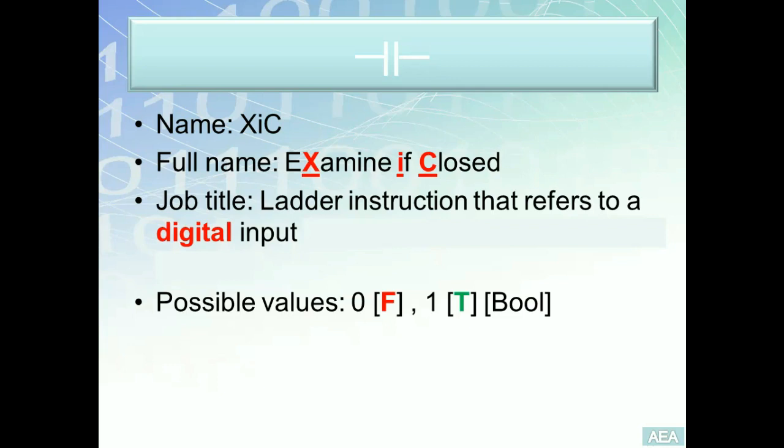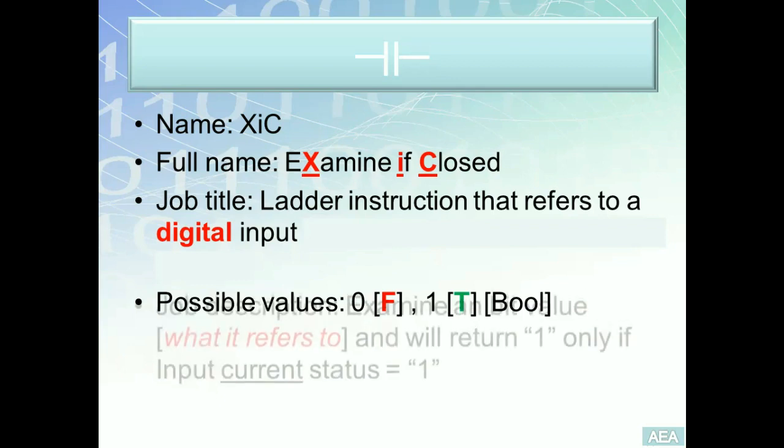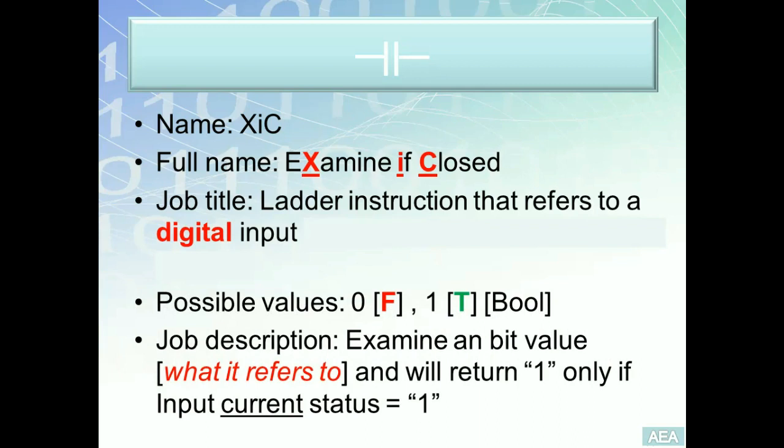The question is: when is this instruction true and when is it false? The answer is in the job description. Each XIC is going to have an address that ties it to an input. This instruction will keep examining — keep monitoring — a specific input. If that input is currently in the closed state, it will be read in the PLC memory as logic one, and this instruction will be true. That's the name: Examine If Closed. If the input is open, this instruction is false. When true, Allen-Bradley will display green bars on both sides of the instruction.